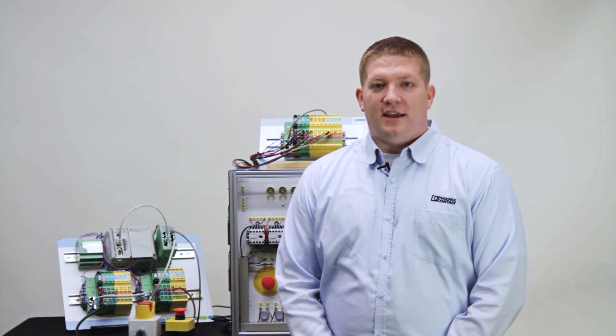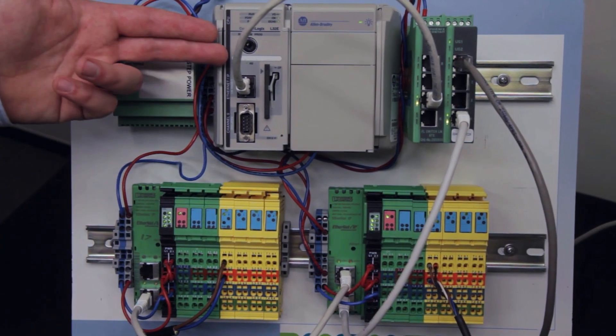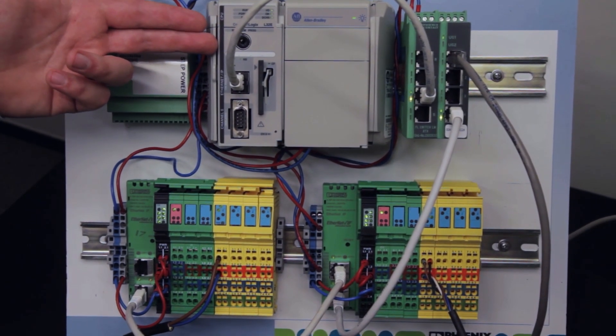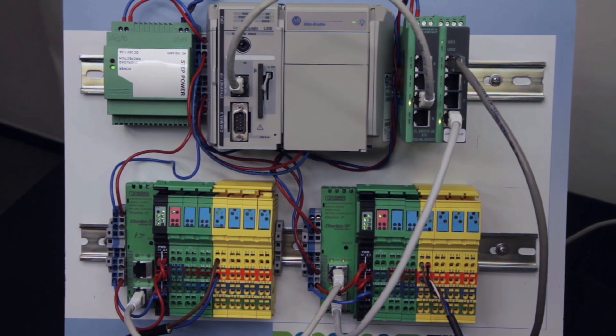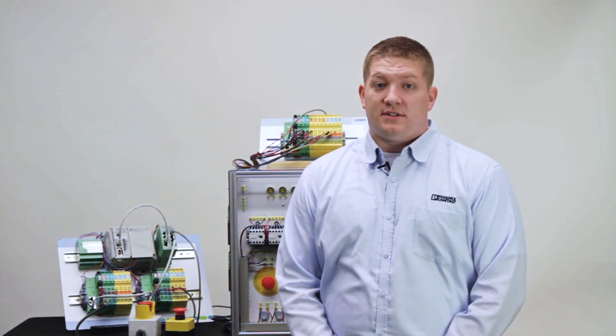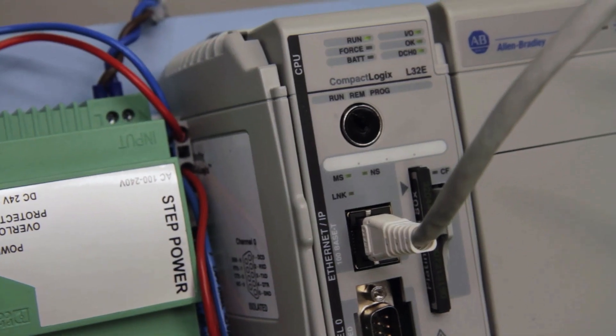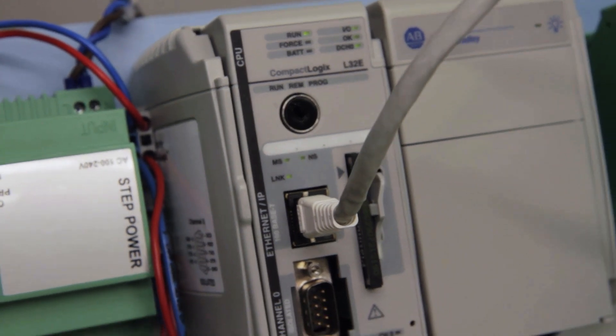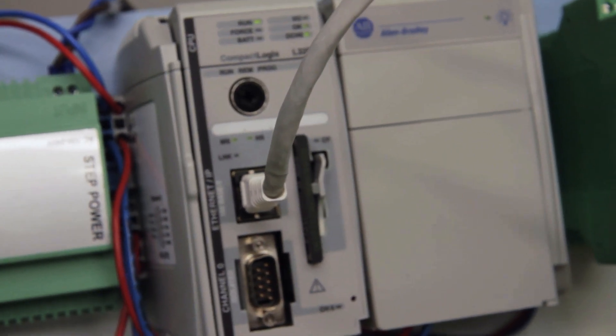This type of communication has several advantages. The standard PLC has direct readable access to all safe input signals coming from the input devices. The standard PLC has direct readable access to all safe output signals which are mirrored as standard inputs by the safe output devices. The standard PLC can directly access all diagnostic information from all distributed safety modules.